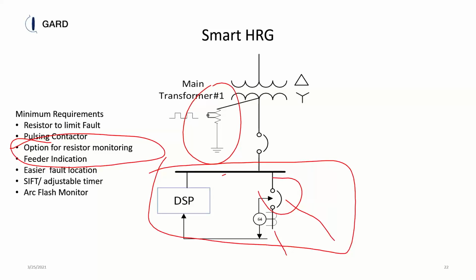And we have an arc flash monitor that you can have in this. One of our customers came to us and said, I like the idea of putting in a resistance grounded system. However, I don't like the idea that I don't get to put a label on my equipment that has lower incident energy. Why should I spend $5,000 to $10,000 on a substation and not get the benefit of putting a new label on there that has lower incident energy? So what we've done is we've created an arc flash relay, which is integral with the resistance grounded system, and we can trip in 1 millisecond if we detect the presence of a fault. So now you can have an arc flash mitigation technique where you can lower the probability of having an arc flash event and lower incident energy. And as the manufacturer of the resistor and the relay, we have the capability of doing that.